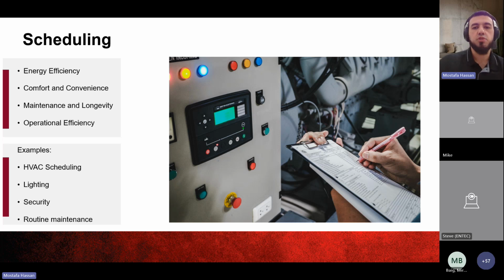Examples of that are HVAC scheduling, right? We have office hours. Program the system to start heating or cooling an office building around 7 a.m., shutting down by 6 p.m. on weekdays. That's going to ensure the building is comfortable only when needed, right, during occupancy times. You also have scheduling of your lighting system. Schedule the lights to turn on at 6 a.m. and off at 8 p.m. Right? And then again, we mentioned daylight sensors. Integrate those daylight sensors to adjust lighting levels based on natural light availability.